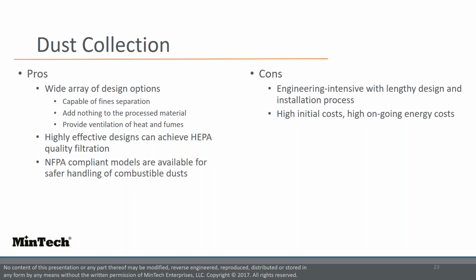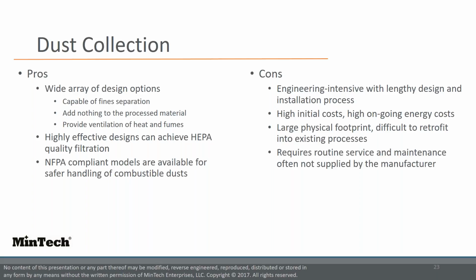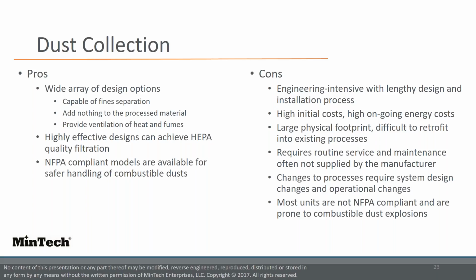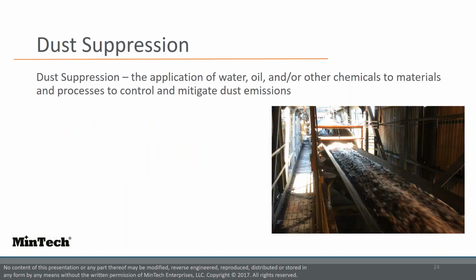And now the cons. Dust collectors are engineering intensive and have a lengthy design and installation process. Dust collectors are also relatively expensive with higher initial costs and higher ongoing energy costs. They are large and they are difficult to retrofit into existing processes. They require routine service and maintenance that often is not supplied by the manufacturer. And if a process is changed, the dust collection system often needs to be redesigned and repositioned in order to accommodate the change. Most units in operation today that are handling combustible dust are not NFPA compliant and have not been updated for safe handling of combustible dusts. And finally, dust that is collected then has to be handled or disposed of, and this often presents further safety or financial challenges.